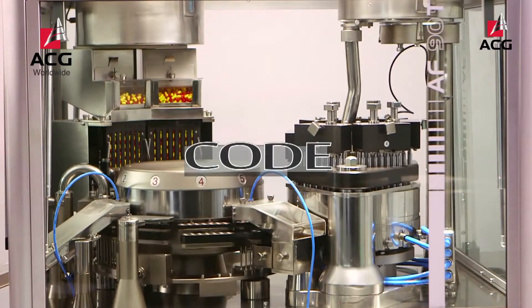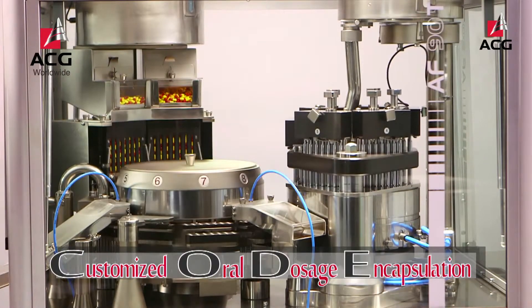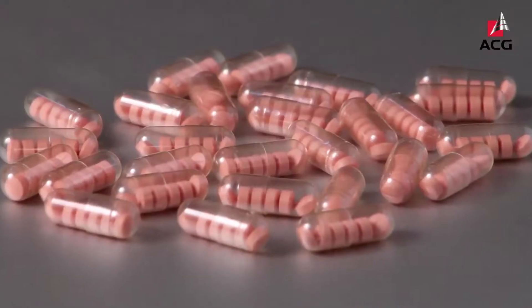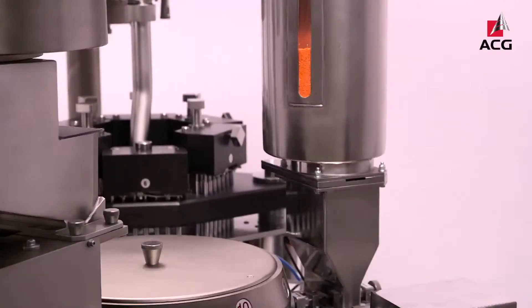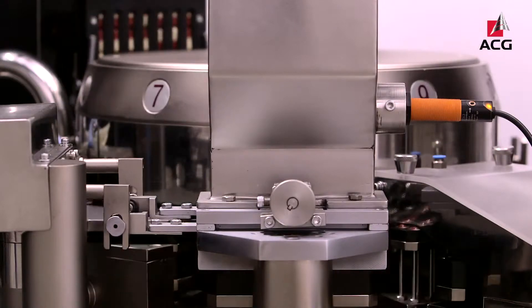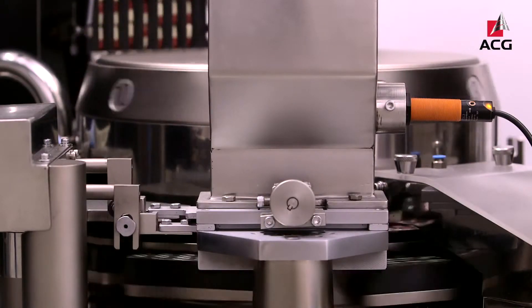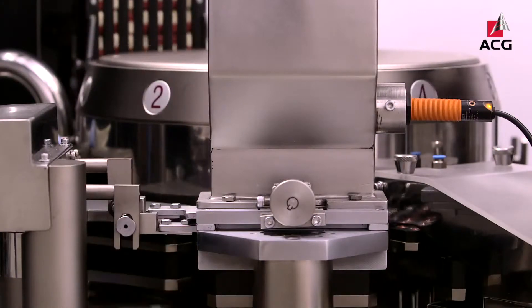A special code team develops unique capsule filling possibilities including dosing of pellets, tablets, and capsules. Pellets are filled using the volumetric filling principle. Intricate components such as level sensors, threaded spindles, and dose chambers are provided for simplified, secure, and accurate filling.